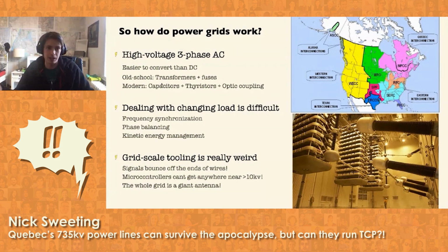Measuring the system is very different than measuring microelectronics. They use tools where you can bounce a signal off the end of a transmission wire and watch it come back, measuring how long the wire is and whether there are faults in between, because any change in impedance causes a reflection. In the same way waves bounce off the end of a pool, signals bounce off the end of a wire. So they send signals down wires to see where the wire went down - it's like, oh, at kilometer 236 - and then they send out a car or a helicopter to replace that part.